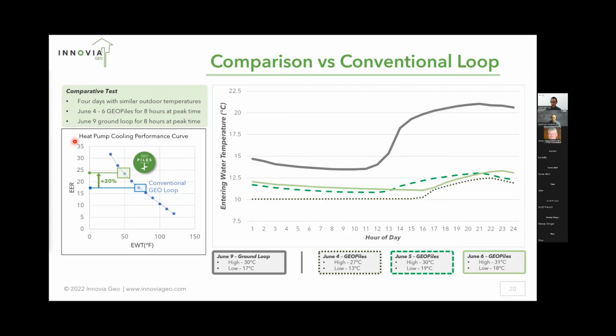And when we look at the efficiency curve of the heat pump, what we can see is that by keeping that entering water temperature in that tighter range, we're actually able to operate the system about 20% more efficiently than the conventional geothermal loop. And this is part of the testing we're going to be doing over the next year, is really trying to understand this thermal storage property, especially considering a building's heating and cooling load profile is never really too consistent. And so all our systems are designed to meet our peak heating and peak cooling days.